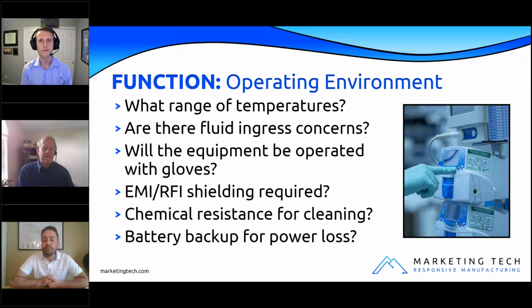Any issues with fluid ingress? Will the equipment be operated with gloves? That's something that a lot of people might overlook just because you want to jump to a touch screen, but as Jim mentioned earlier, if you have multiple layers of gloves on for different reasons, the mechanical feedback from a mechanical switch might be useful.